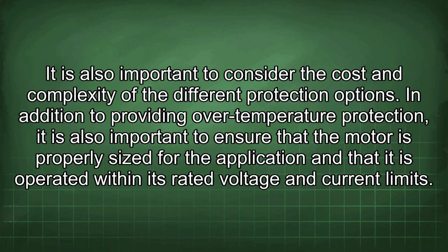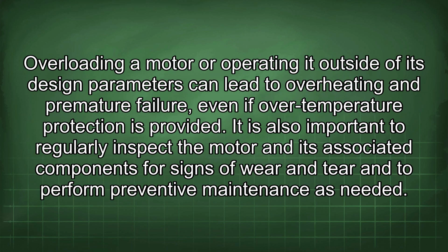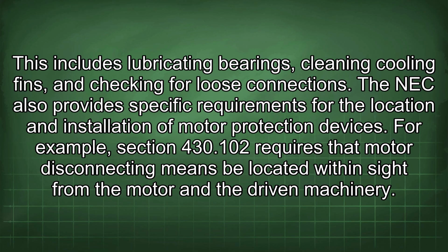In addition to providing over-temperature protection, it is also important to ensure that the motor is properly sized for the application and that it is operated within its rated voltage and current limits. Overloading a motor or operating it outside of its design parameters can lead to overheating and premature failure, even if over-temperature protection is provided. It is also important to regularly inspect the motor and its associated components for signs of wear and tear and to perform preventive maintenance as needed. This includes lubricating bearings, cleaning cooling fins, and checking for loose connections.